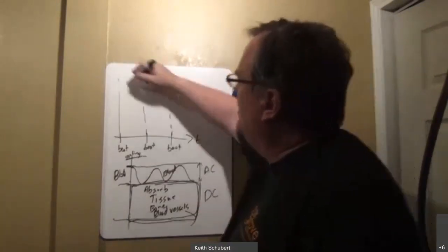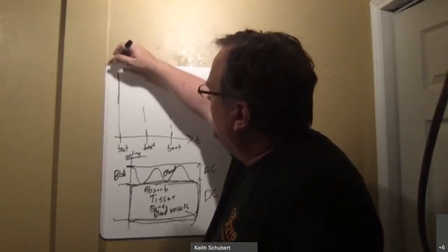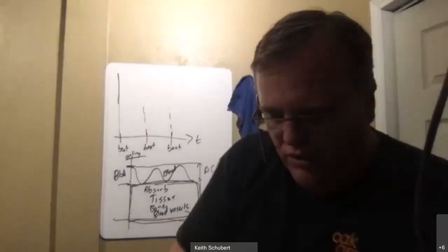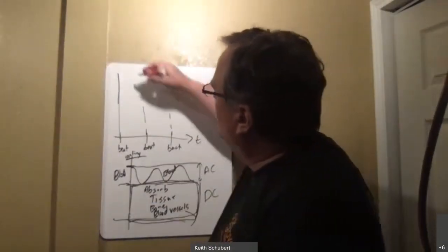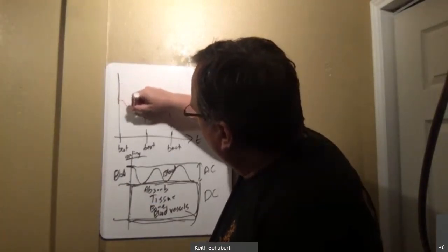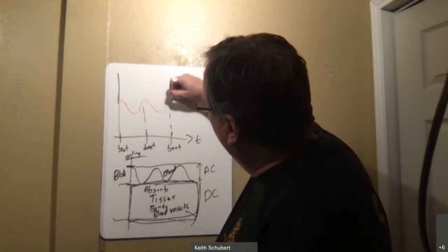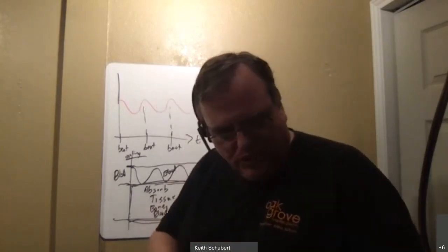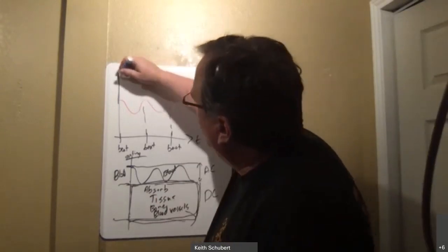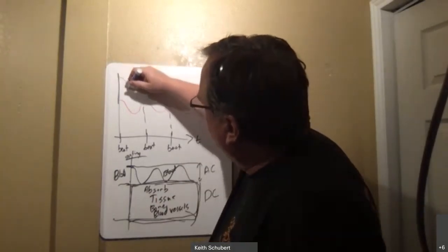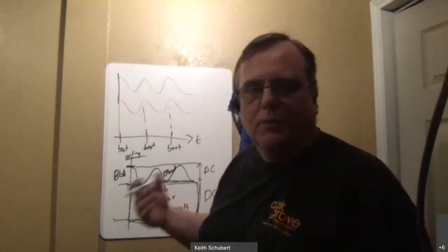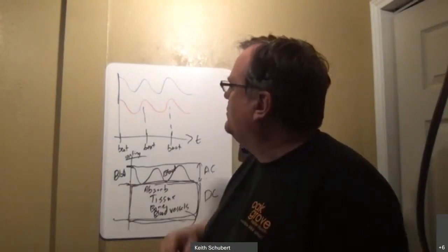If I were to plot, right, for two different wavelengths, I'm going to put red for my red light. So you can imagine I've got my 660, and it's going to be doing its ratio. And further in, maybe I've got my 940, and let's just say for the sake of argument, it's just a little bit above it, right? A shifted and displaced version.